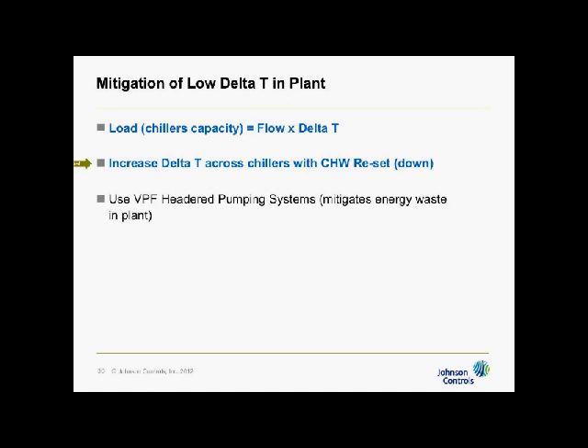You've got to do something with one of those two in order to mitigate the negative impact of low delta T. Okay? I can increase the delta T across the chillers. Well, I can't really change the return. I can change the supply. I can lower the supply down 3 degrees when I have a 2-degree delta T problem and pick that 2 degrees back up. I won't pick up 3, but I will pick up 2 because the water going down 3 degrees here would be 37 degrees going to the coils. The coils would respond with a much better heat transfer characteristic that's nonlinear and actually pick up and pull 2 degrees out, so I'd have 36 to 53. I'd get my 16 degrees back.